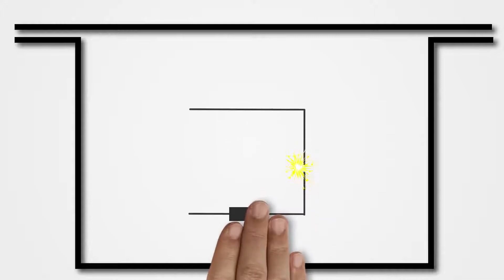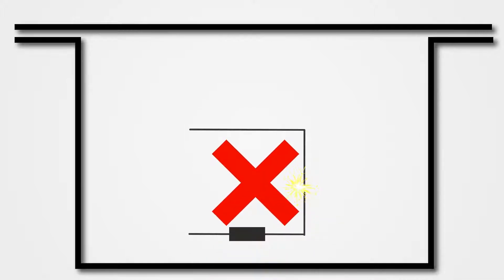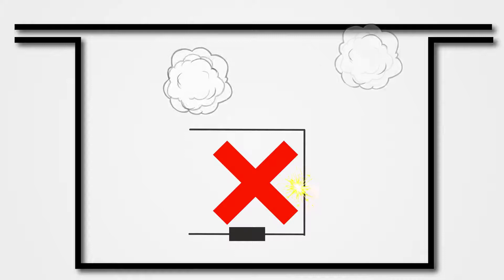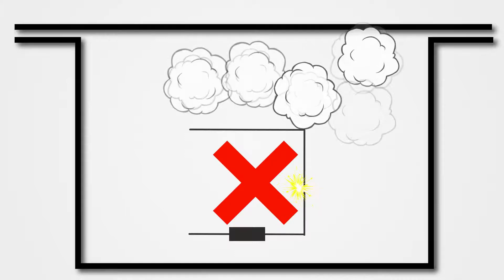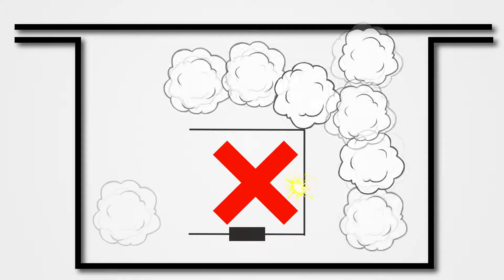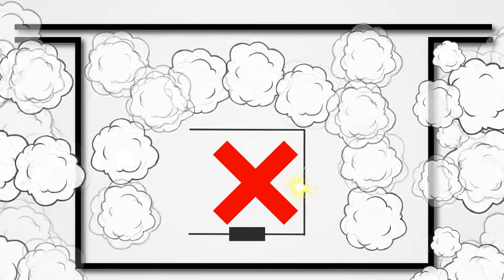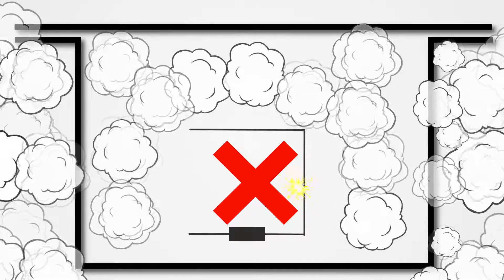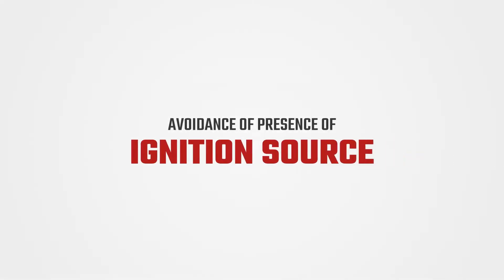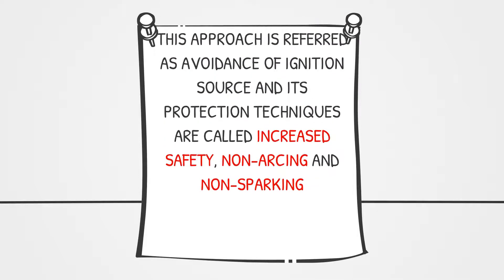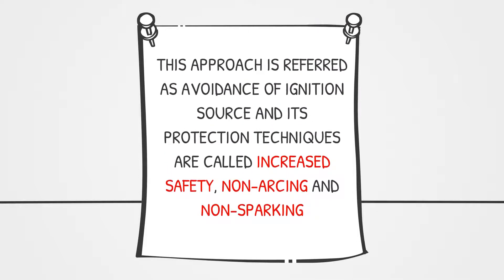And finally, some electrical devices and their components are, by design, non-arcing. They do not contain any arcing or sparking parts, and all hot surfaces are identified and controlled to be less than the ignitable temperature of the surrounding gas. There are no sources of ignition inside the device's enclosure, so this technique is called avoidance of presence of ignition source. This approach is referred to as avoidance of ignition source, and its protection techniques are called increased safety, non-arcing, and non-sparking.